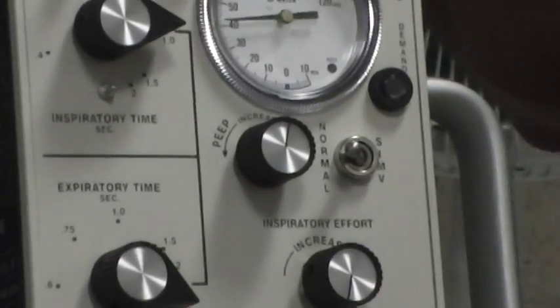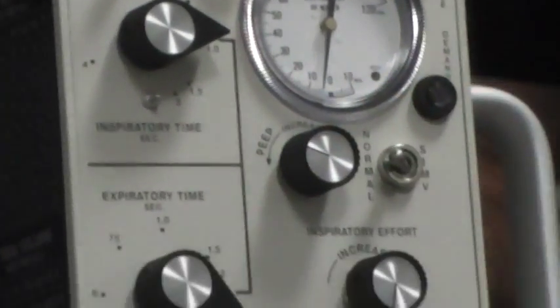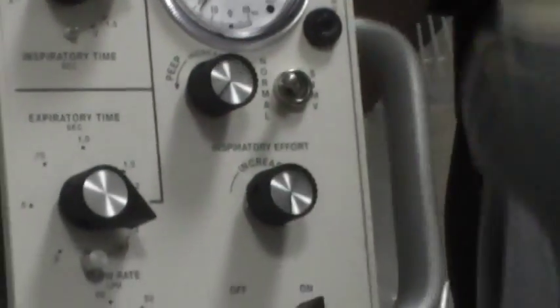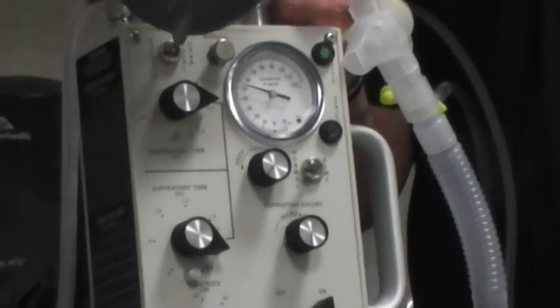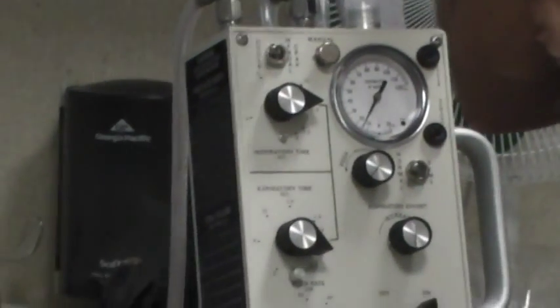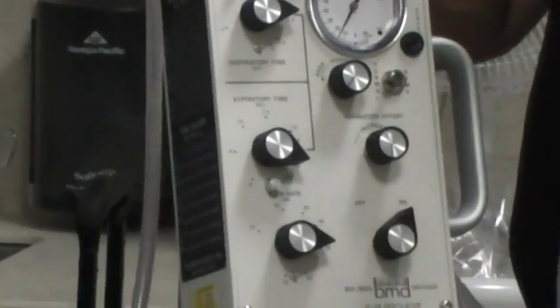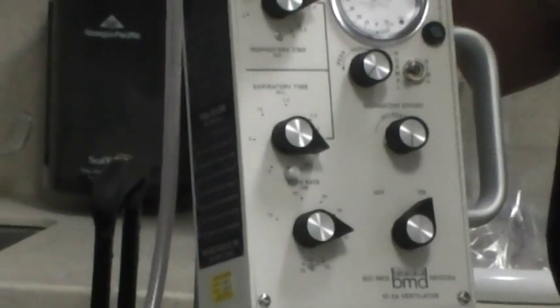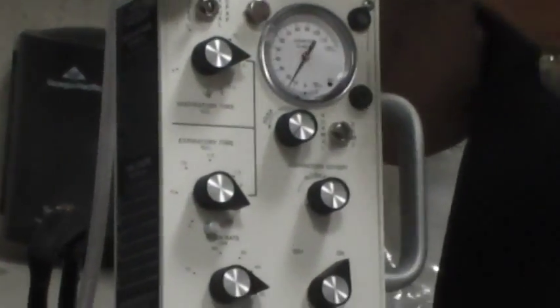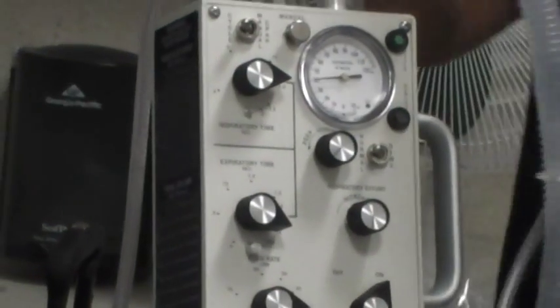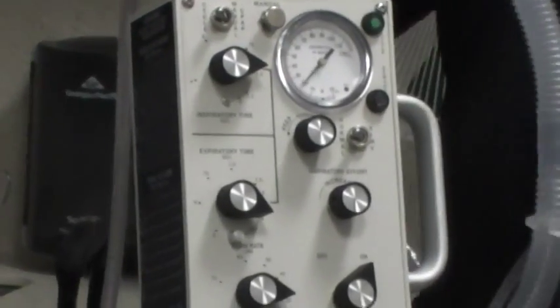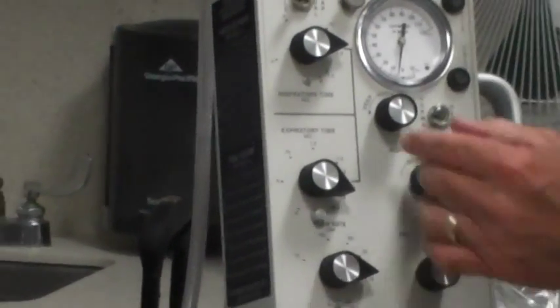Now I'm going to turn this up just to let you hear this. I turn my PEEP way up. Hear that honking noise? It's because I'm pushing a lot of gas through this exhalation valve. If you were going to measure volumes, you could hook up the sensor here, and you'd want to do that outside of the MRI. You really don't need that valve unless you're going to measure. By taking it off, you usually get rid of that honking noise. It kind of acts like a megaphone when it's on there.